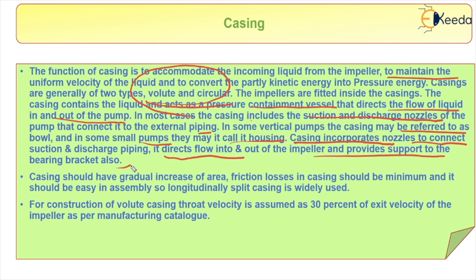The casing should have a gradual increase of area, friction losses in the casing should be minimum, and it should be easy to assemble. Longitudinally split casing is widely used. For construction of a volute casing, throat velocity is assumed as 30% of the exit velocity of the impeller, as per the manufacturing catalog.